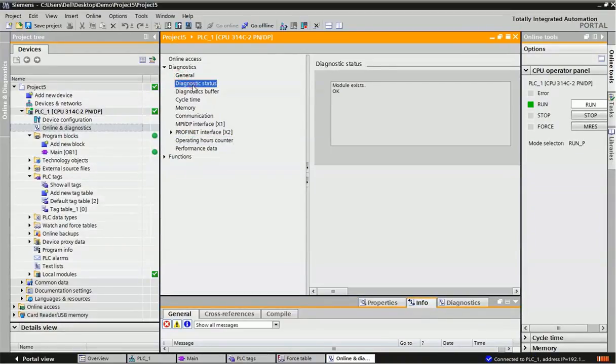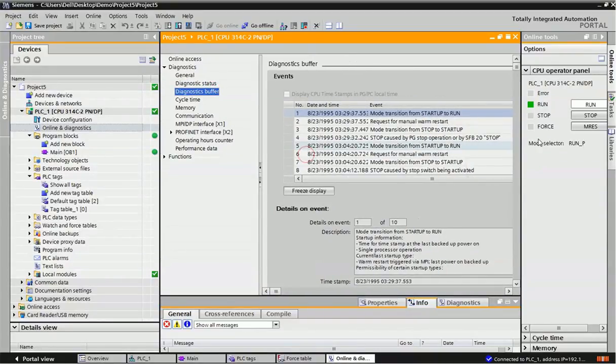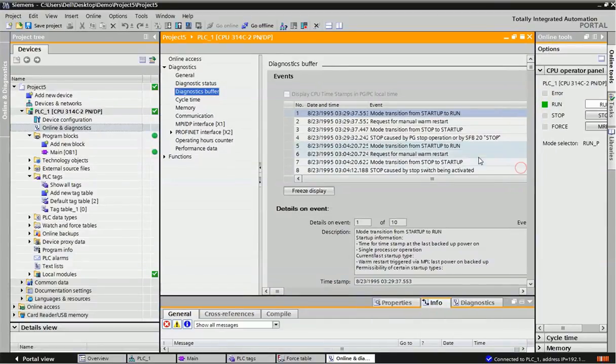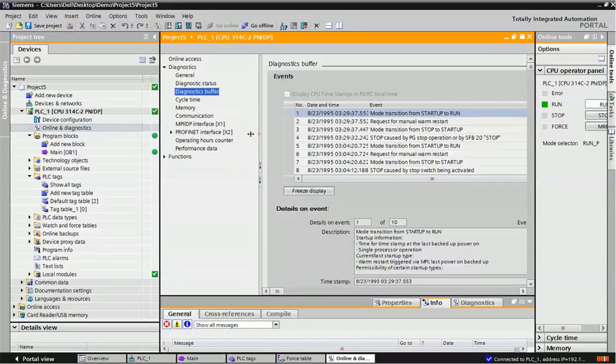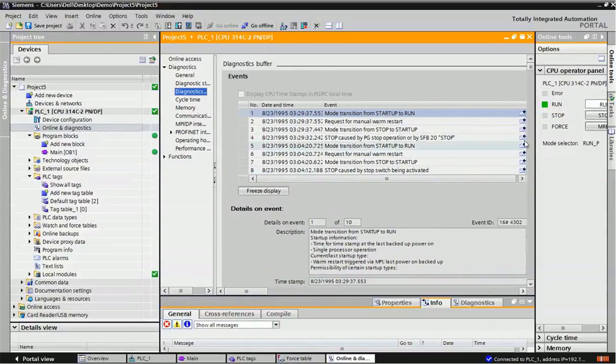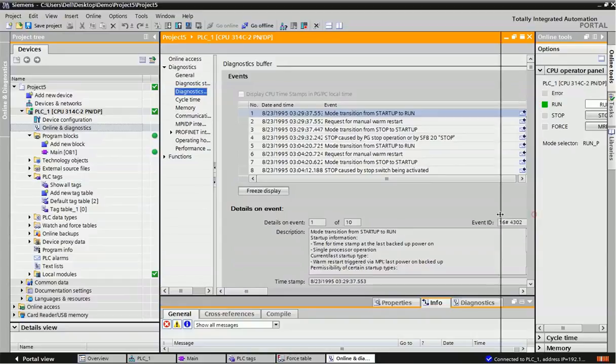Diagnosis status will indicate here. From the buffer you will get information if PLC is in stop mode or run mode or if there is any fault, you will get the notification or message here. This diagnostic buffer will give you remedy option also here, so how you can rectify the problem as soon as possible.